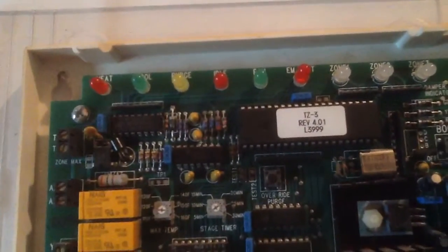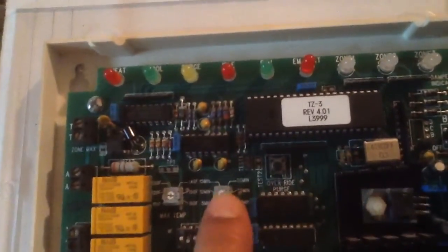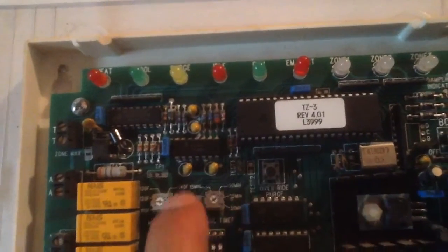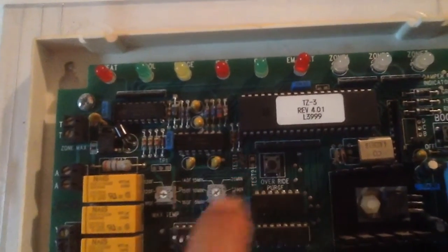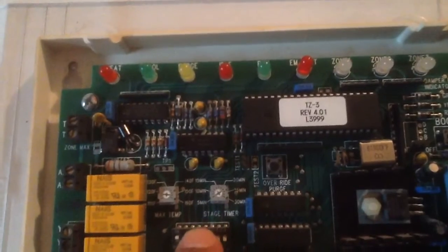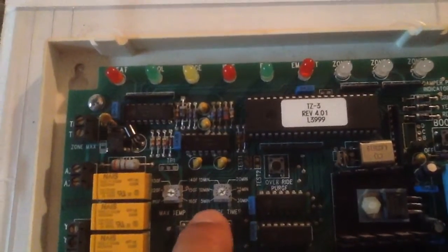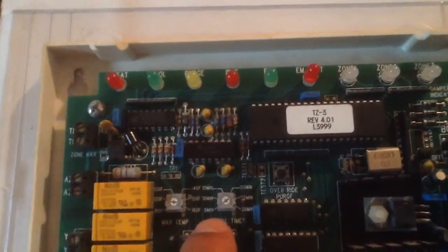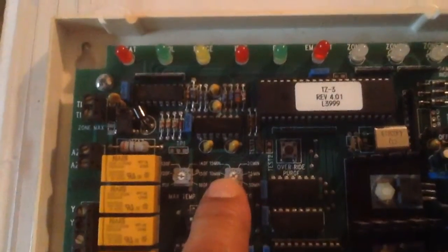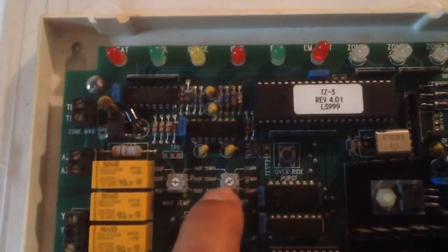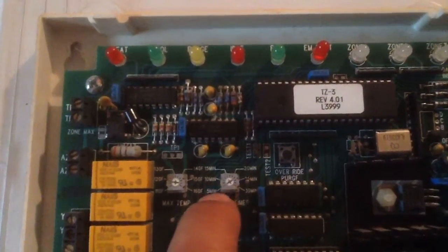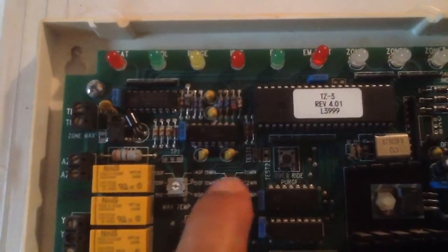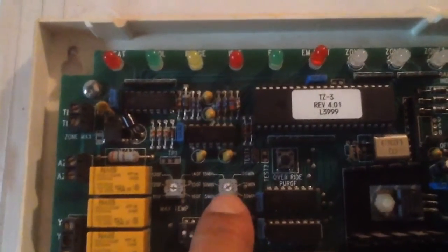That's pretty much what that's there for. And then you've got your stage timer here on the right side, and you'll notice you have some time there, and that's basically your second stage timer. So when you get a call for first stage heat through the zones, let's say you have this set for 5 minutes, they'll go through a 5-minute timer, and if you still have a call for heat, it'll bring on backup heat. And that's for the most part it.